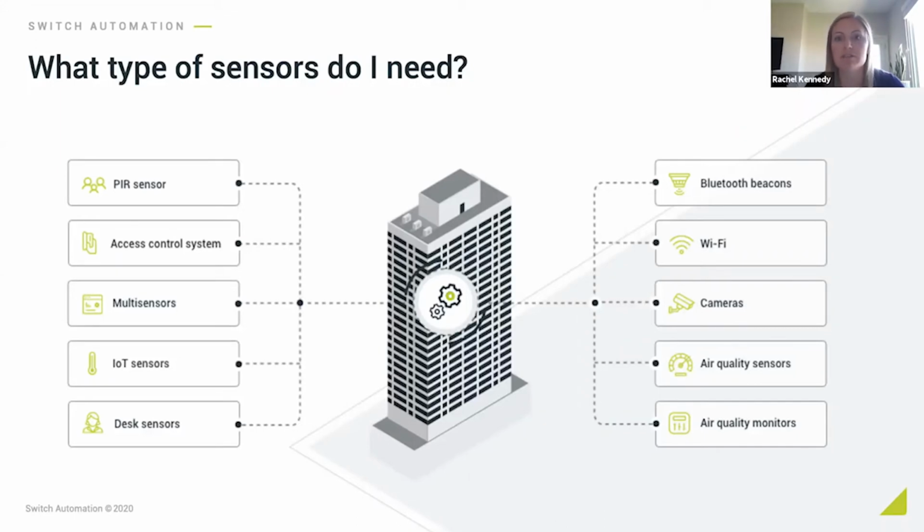When we think about some of those different multi-sensors, a lot of the pros are that they have multiple different data points within one sensor, but they often require a retrofit, or you're going to want to be installing them separately. It does allow that flexibility of not necessarily needing some infrastructure underneath, because they can communicate wirelessly, or you can run power and data directly to that sensor. That does provide the bonus of high granularity. You're not requiring active users, or in the cases of Bluetooth beacons and Wi-Fi, that people have those turned on. We're going to capture those measurements of the people for occupancy in both cases.